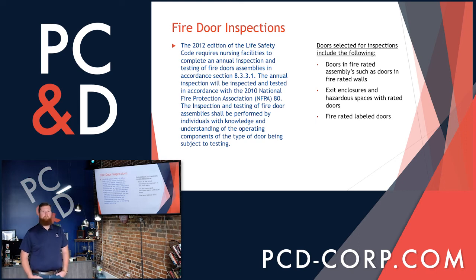Touching back on the fire door inspections real quick, as of 2012, within your active zones of your community, obviously smoke and fire can penetrate from one zone to the next. The fire door is the only thing that keeps that at bay, unless of course you have a penetration-ridden community, which we hope you do not. These inspections are very crucial to the safety of residents from one area to the next, and therefore must be completed on an annual basis.